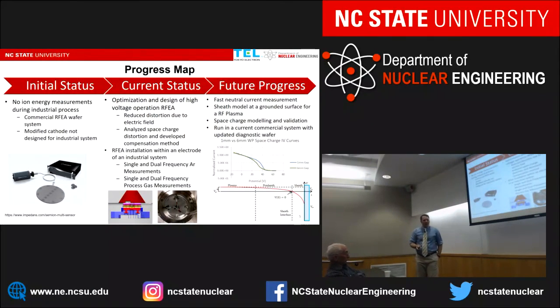So when I started, they had done retarding field energy analyzer measurements in the past. They have wafers like these, where it's an actual wafer that you can put on top of the electrode and get multiple IEDFs. However, this isn't really conducive. One, it might not be very resistant to chemical shock, and two, you can't put it in the machine because the machine has robots that take the silicon wafers, put them in, and run it. So you can't necessarily do that with this wafer.